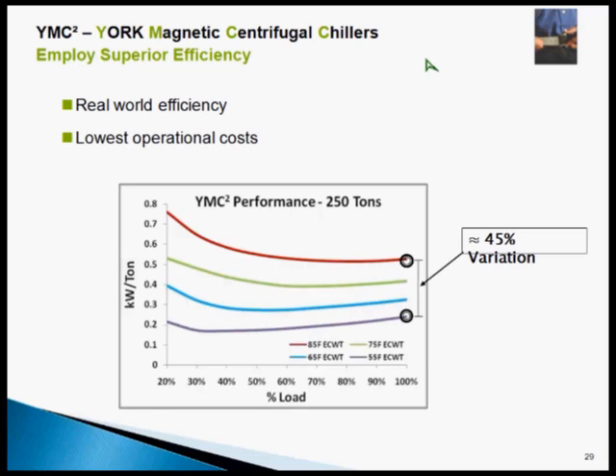So look at this. Look where my finger is coming out in kW per ton. 0.3, 0.4. That's half of what a typical chiller uses. So, good news. The thing that uses 40% of a building's electricity, the chilled water system, is now getting more and more efficient. But remember, we went through the discipline of proving that the time for a retrofit was now. We needed to go through all those other steps.